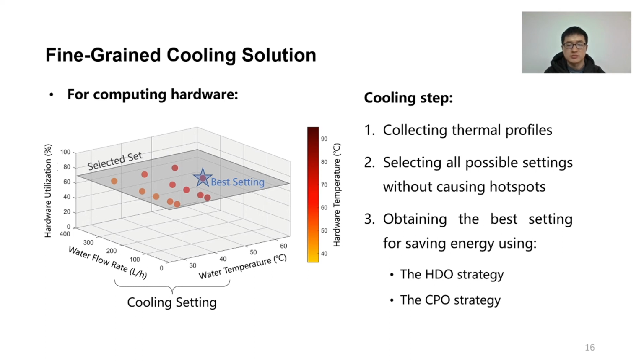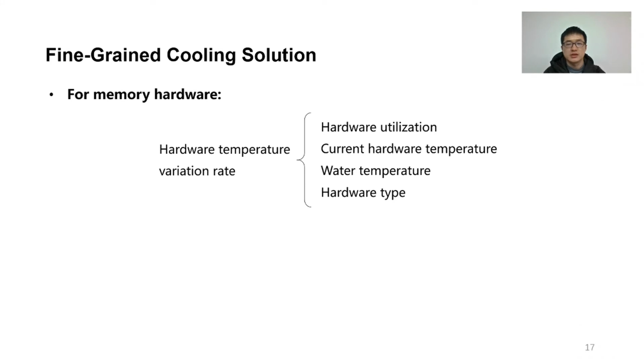cooling energy. For the memory hardware with the low power consumption, the water flow rate has little influence on the hardware temperature, as the generated heat can be timely taken away, whatever the water flow rate is. As for the water temperature, it directly influences the hardware temperature variation rate. The temperature variation rate is defined as the reciprocal of the time spent to raise or reduce the hardware temperature by 1 degree Celsius under the specific hardware utilization, current hardware temperature, water temperature, and also the hardware type.